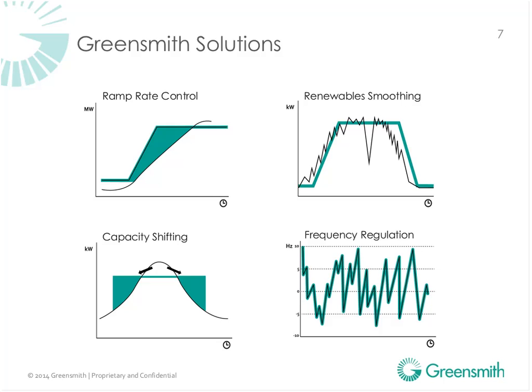So an additional usage is this power factor correction, or the ability to put reactive power onto the grid at whatever level you need. The added benefit versus just setting the solar inverters at a set point is you can put a CT or a PT clamp on the grid, and actually determine what level of VARs you need to put on. So you can be even more dynamic.